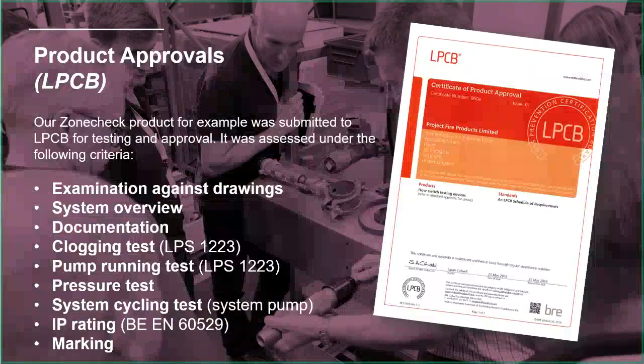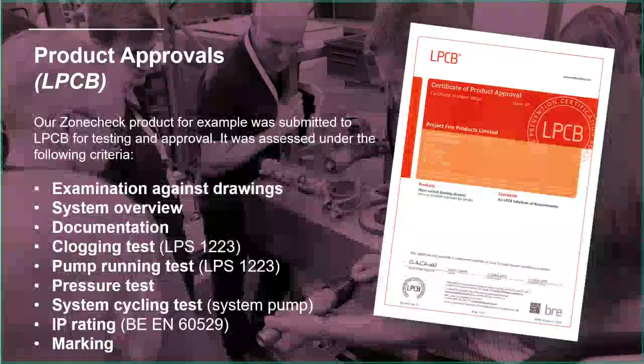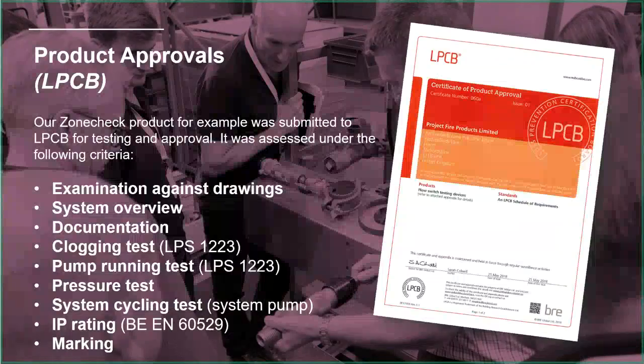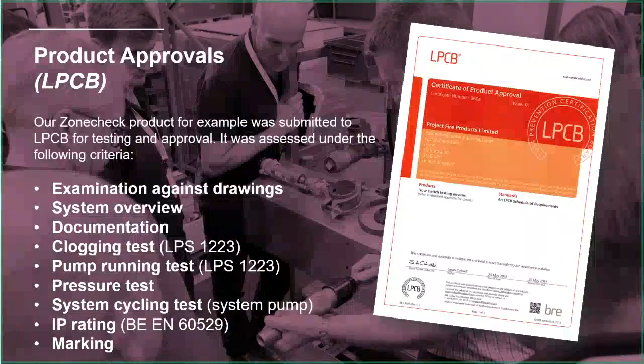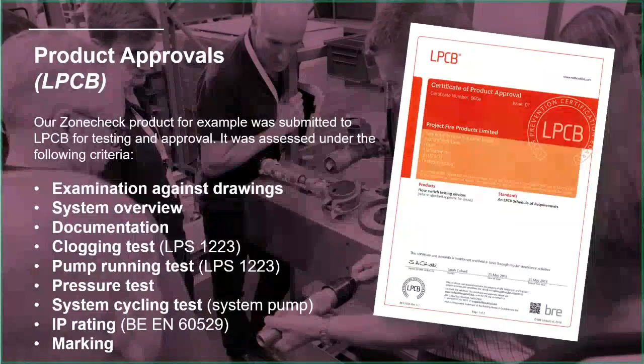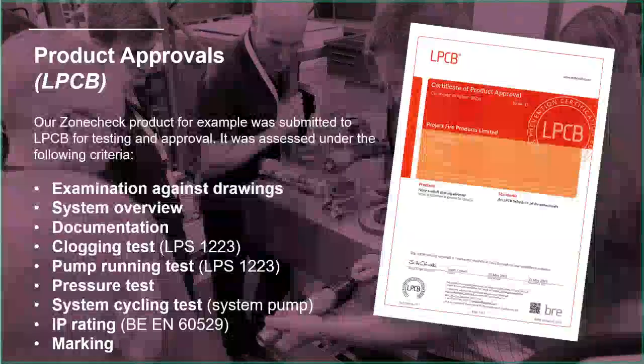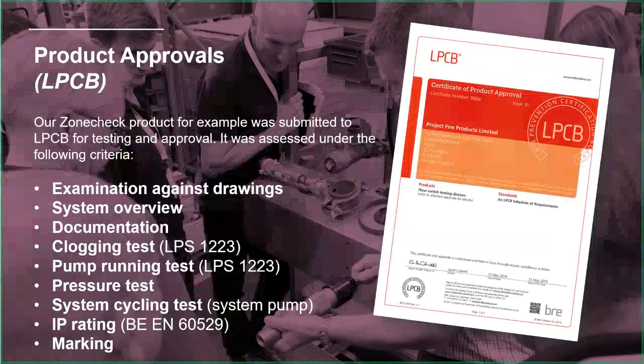Pump running test. They run the pump for a long period of time. Zone Check is only designed to operate for about 1 minute at a time, but they test the pump to several hours of operation to make sure that it's reliable. Same with the pressure test. The actual working pressure of a Zone Check is 12 bar. We test it to higher than that, and the LPCB test it to even higher still. If it doesn't break at 25 bar, it's definitely going to be good at 12 bar. They also do a system cycling test, turning the pump on and off, on and off, simulating a whole life cycle and again checking the product is robust.